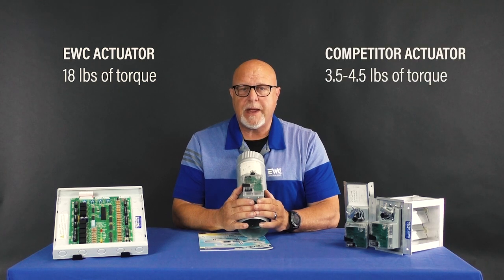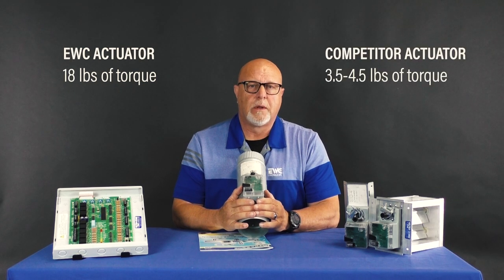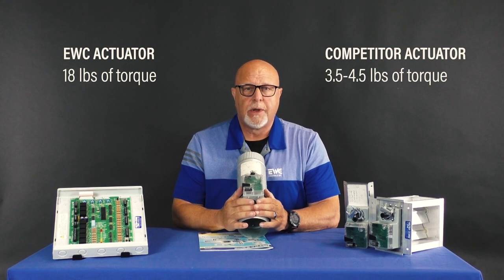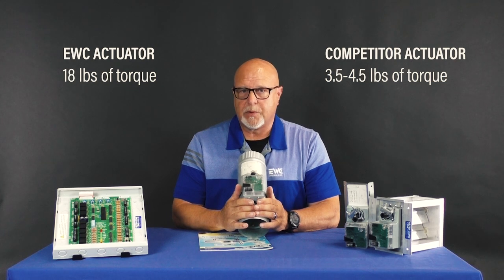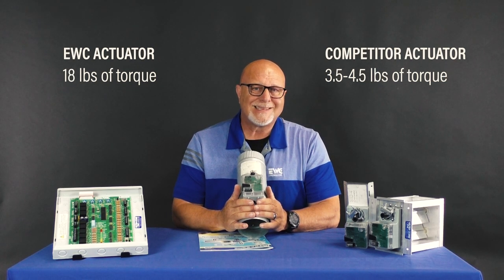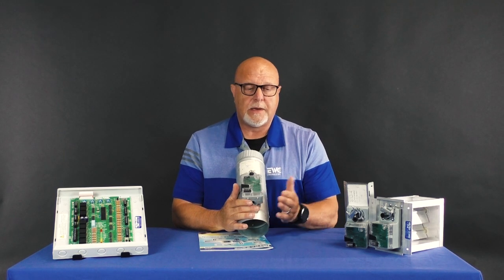Most of my competition out there that are 2-wire spring return dampers are between 3.5 to 4.5 pounds of torque. I am 4 times stronger than my nearest competitor, and I am also able to handle higher static pressures. In those instances where I am exceeding 1 inch of static pressure, most of my competition has a hard time opening or closing. With the EWC damper having 18 inch-pounds of torque, I can easily handle over 1 inch of static pressure. We advertise and commonly will handle static pressures up to and including 1.5 inches of static pressure. So therefore, we can operate in your residential and your light commercial zoning world.